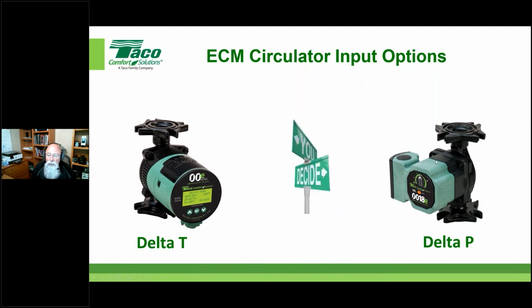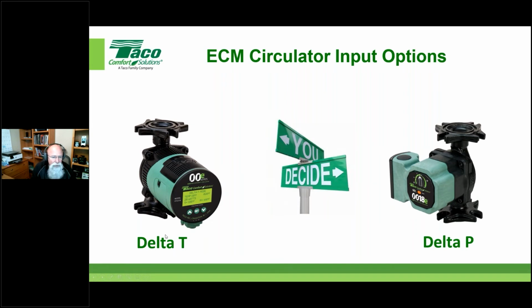Okay. And we'll give you enough information so you can make a good decision on when to use what mode of operation. This is not so much saying when do I use delta T and when do I use delta P. Primarily what we're using in this industry, except on rare occasions, is pressure differential. And that's what most of this training is going to be on.